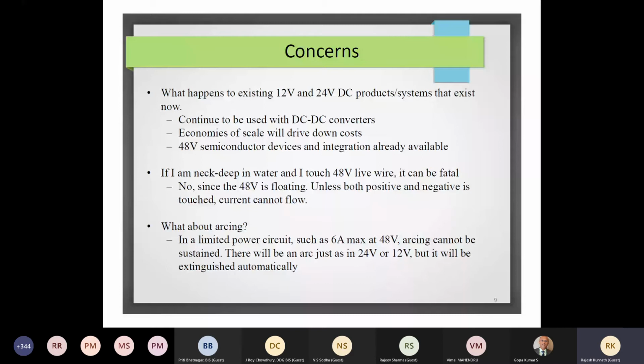What happens is, let's say there's a small insulation fault, you cut the wire and bring two wires together, there's going to be an arc. When the arc has sufficient energy to propagate, it's able to melt the insulation and pass over it. But in the case of DC, what we found is that with these limited powers, the arc cannot propagate continuously. There have been research papers that have vindicated our approach. So arcing is not an issue.